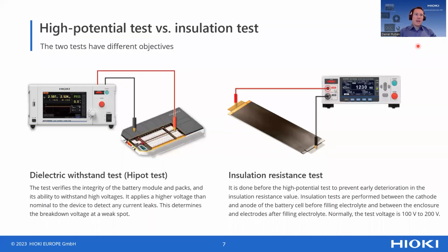Dielectric withstand test, Hipot test, safety test - these are the terms for a final test on an assembled pack or module. This product is completely focused on the battery industry, which is why we show the application on a battery module. It is necessary for a producer, or even at the R&D stage, to ensure first that the battery has higher integrity in terms of withstand, and also that there are no issues with insulation.